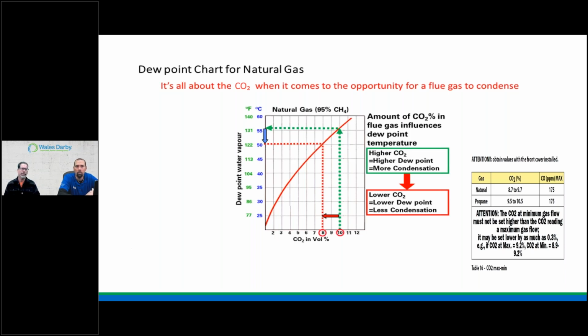scale or early slide. All right, so lower CO2 equals lower dew point equals less condensation. So we're getting colder returning water, we're still not condensing. So therefore, you might want to shift within what the manufacturer recommends, okay? So higher CO2, higher dew point, more condensation, okay? So it's a cooler approach to understanding the inner workings of what we're doing with the strategy on board, all right? Using outdoor temperature, monitoring our demands, return water temperature, and all this stuff is being driven, and the dew point will drive our efficiencies higher and higher, all right?